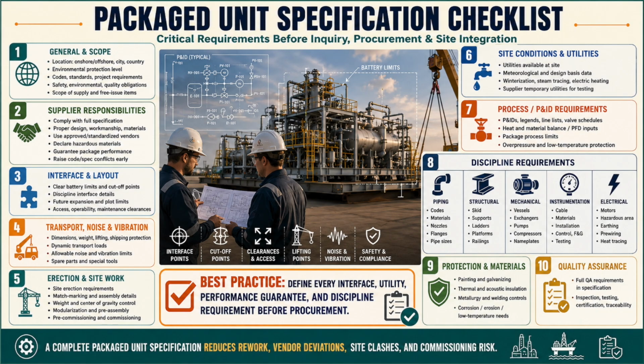Define supply and return conditions, allowable pressure drop, chemistry and fouling assumptions. Specify winterization, steam tracing, electrical heat tracing, freeze protection, and cold start requirements. Consult construction and contracts teams for site-specific restrictions that design engineers may not see. Also state that the supplier must provide any temporary utilities needed for construction, testing, or pre-commissioning, unless the project explicitly agrees to provide them. The process definition begins with P&IDs and associated documents.